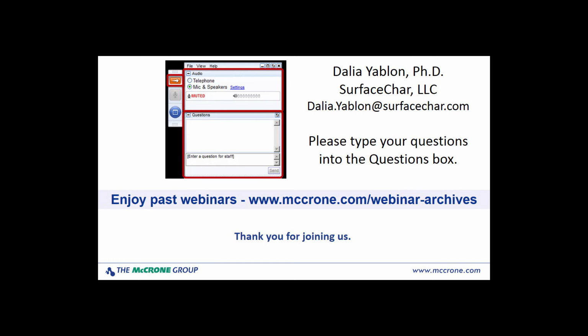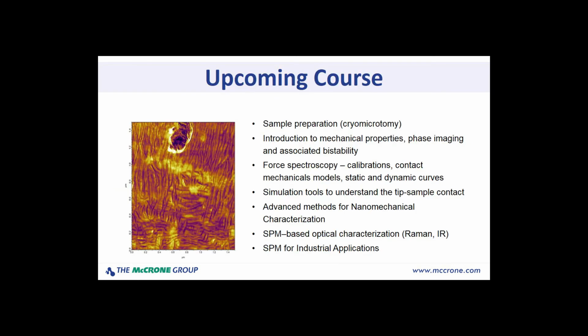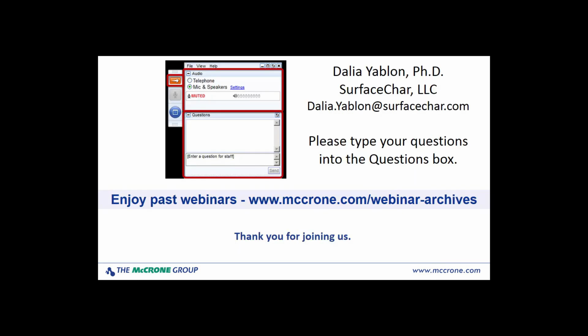If you can immerse your sample in a liquid, that really helps get at that higher resolution. I don't push atomic scale resolution because it's not something that's applicable to any sample that you throw in under your system. It'll also need to be well prepared. But in terms of the limit of topography, on these research level commercial instruments, it is atomic scale, provided that your sample cooperates and you're willing to operate in a more sophisticated mode.